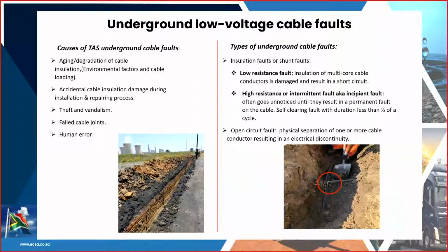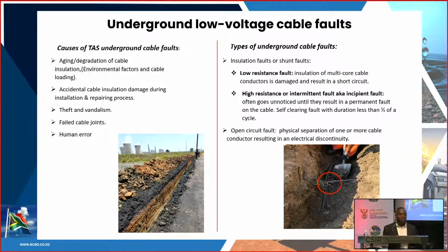The open circuit fault is not really of interest to me or any other researcher, because in this state the fault has already occurred. There's nothing more you can do. There's just a physical separation between the conductors. All you can do is replace the cable. Now we need to go back to the shunt faults. We can break them down further into 2 categories, the first being low resistance faults. This happens when there is a short circuit between one or more cores of the cable.